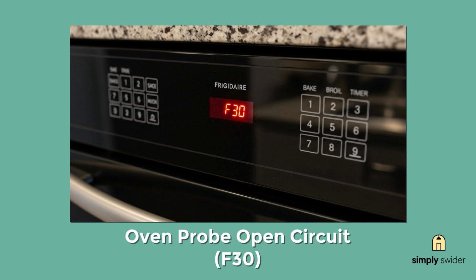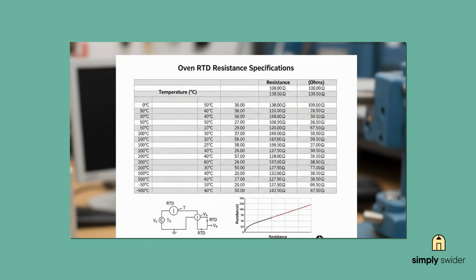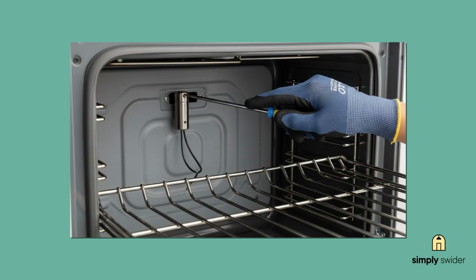For the F30 on ranges, power down the unit for 30 seconds to reset it. Then test that sensor resistance like I showed you before. Should be around 1100 ohms at room temperature. If it's not matching the RTD chart specs, swap out the sensor probe. Now here's something most people don't know. If the sensor tests good but you're still getting F30, that means the relay board itself is defective.